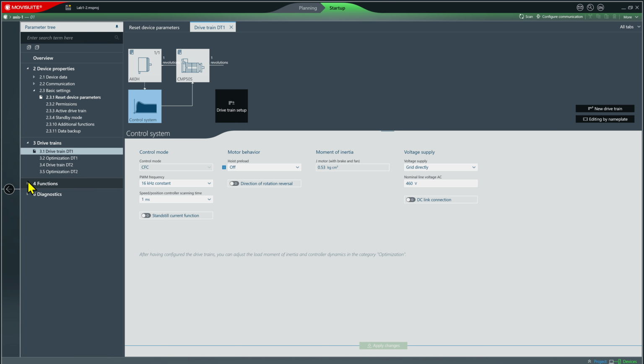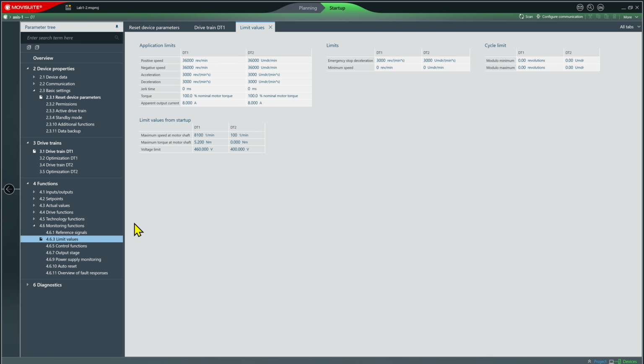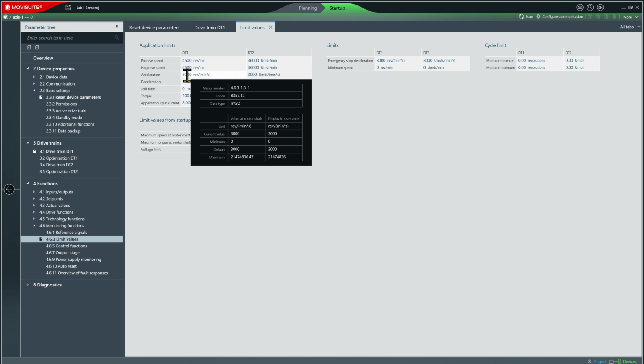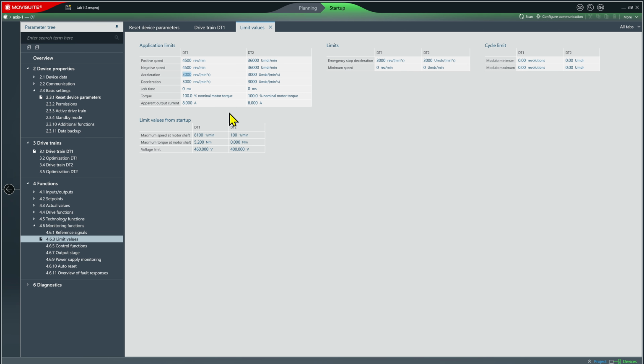I'm going to now expand my Functions menu and pick Monitoring Functions submenu, and then open Limit Values. And I notice my motor speed is set unrealistically high, so I need to set this. I'm going to set it to 4,500 RPM, which is the motor's nominal speed. I need to set it for both directions, clockwise and counterclockwise. I also need to pick acceleration and deceleration values, and according to my instructions, it says just set it to double the motor's speed. I'll set it to 9,000 RPM per second. That's just an OK generic value. All right, so that establishes some limits on my motor.